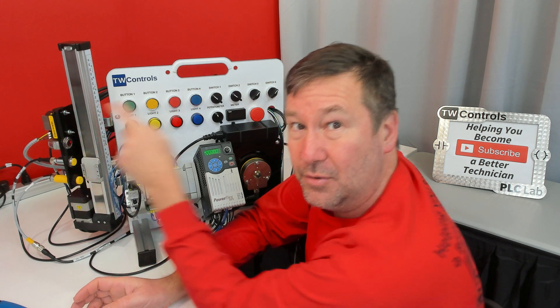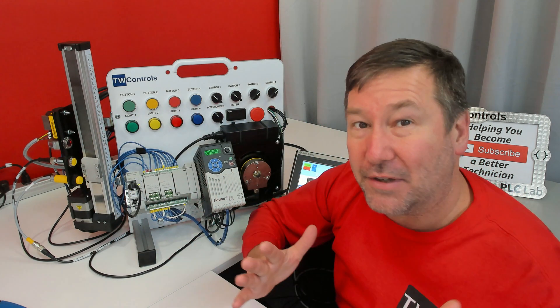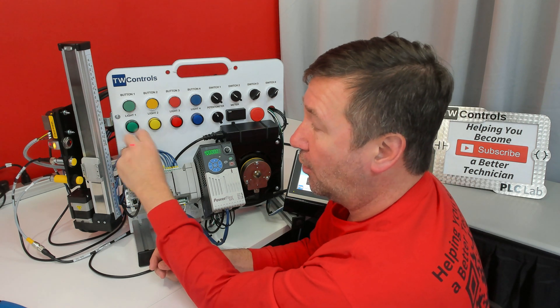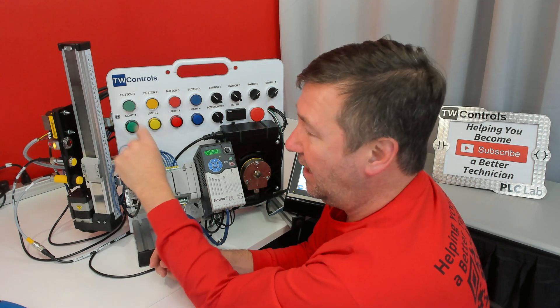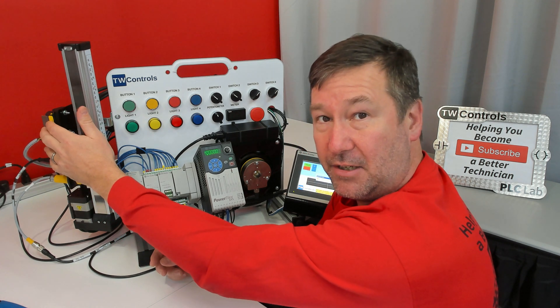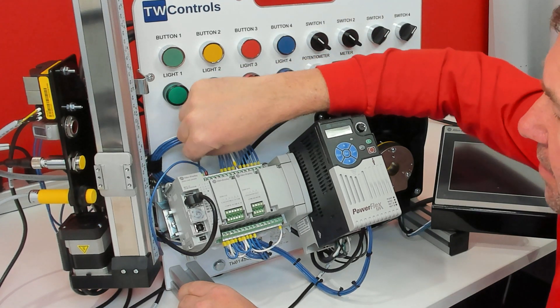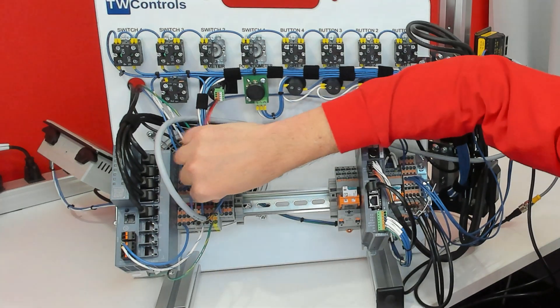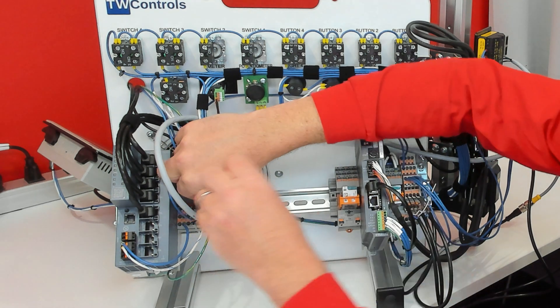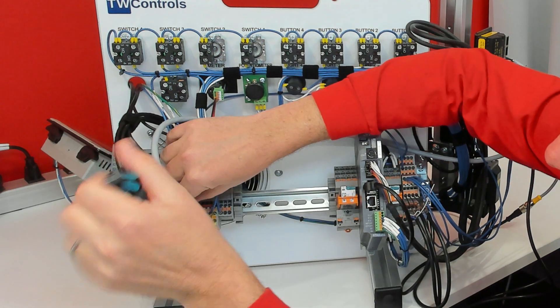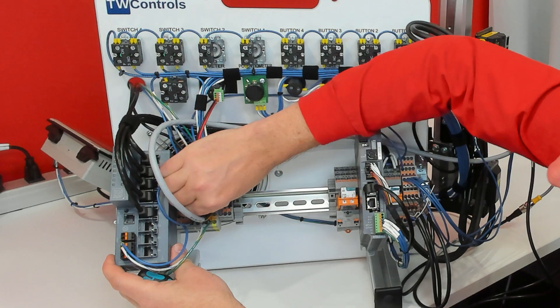Now, since we have the laser that can do push-pull, that really is NPN or PNP. Let's go ahead and take off our inductive prox and our capacitive prox, and just go ahead and put them back on the IO-Link where they were. And now what we want to do is we want to take the COM0 wire, which currently I have connected to the minus terminal block, that right-hand set of terminal blocks. We're going to take it off, and we're going to put it on our plus terminal block.